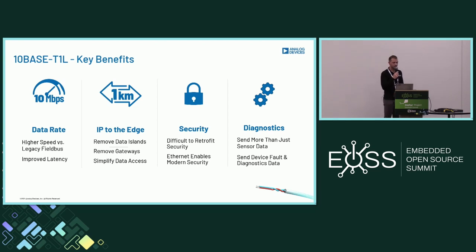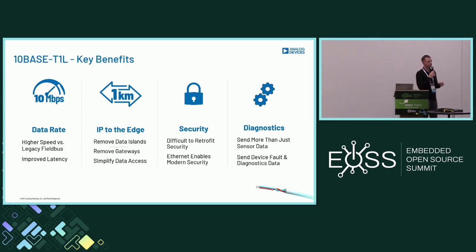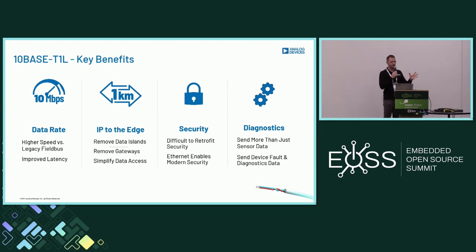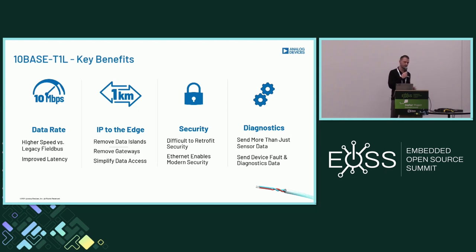Next is security. In the industrial space, as the IT world and the OT world — operational technology, the factory floor — converge, security becomes increasingly important. The ability for external attackers to access OT technology through the IT domain increases, so modern cybersecurity techniques must be deployed to the operational network. Finally, diagnostics: ethernet is full duplex, whereas legacy fieldbus protocols like RS-485 are often half duplex and can only send limited data. With ethernet we open the door to more complex device-centric diagnostic data and even implementing over-the-wire firmware updates.